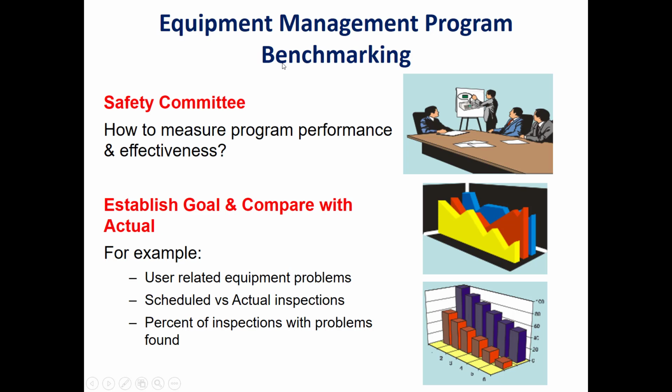Another policy and procedure is benchmarking, or the study of the performance within the clinical engineering department. It is how to measure the program performance and effectiveness. Usually we use what we call performance indicators. For example, such performance indicators are user-related equipment problems, the scheduled versus the actual inspections, and the percent of inspections with problems found.